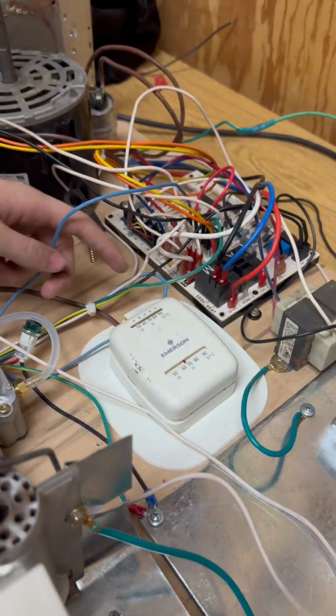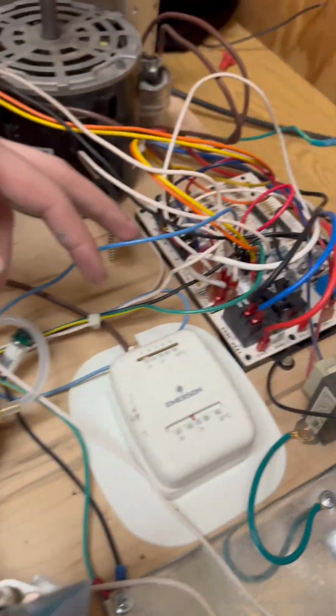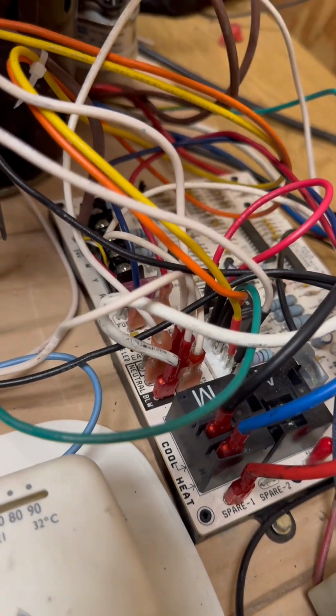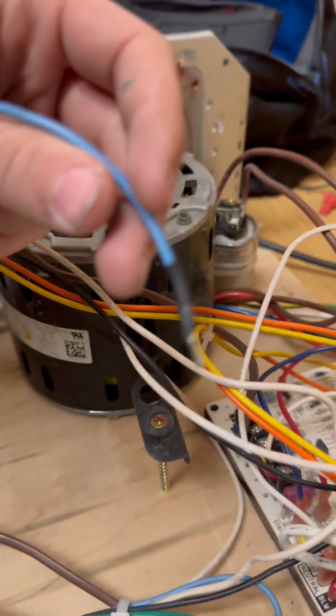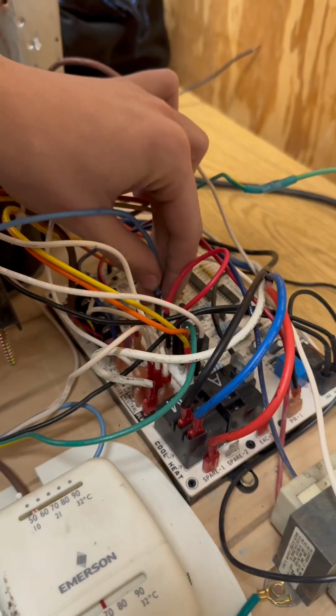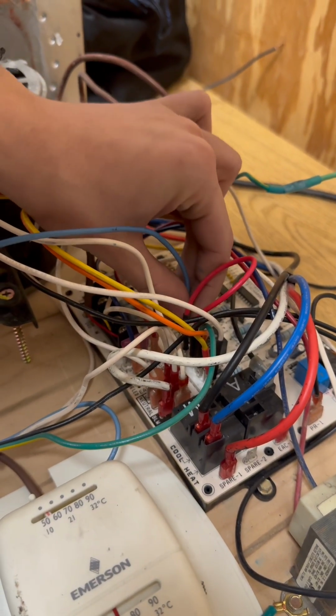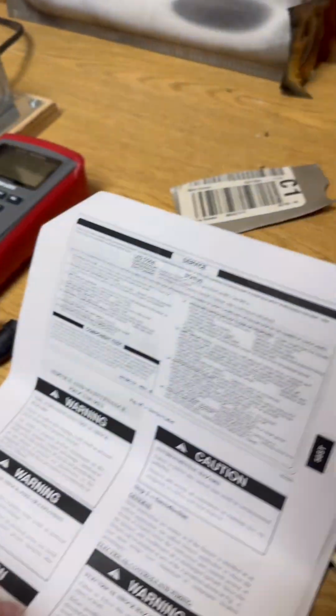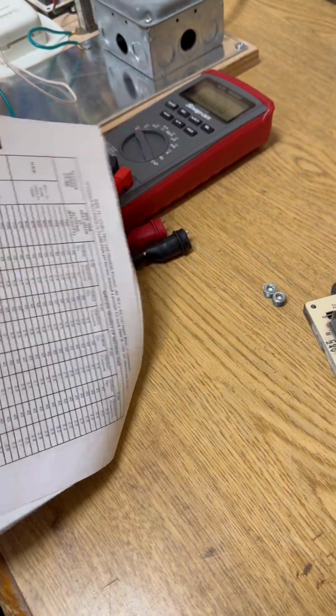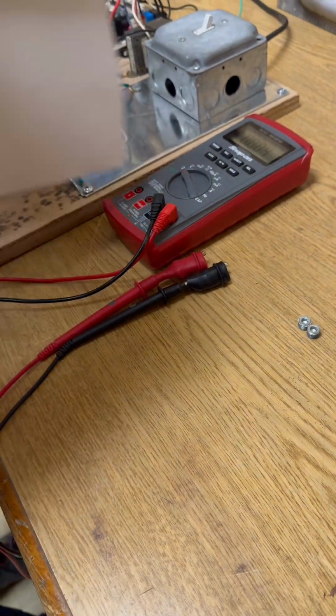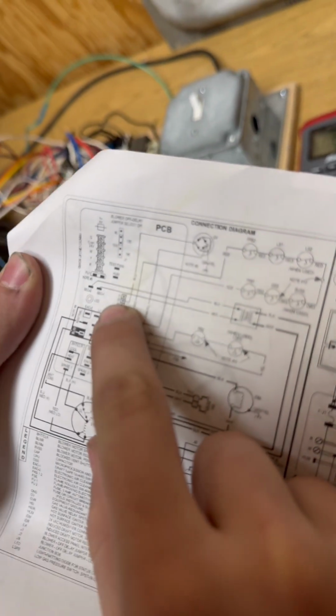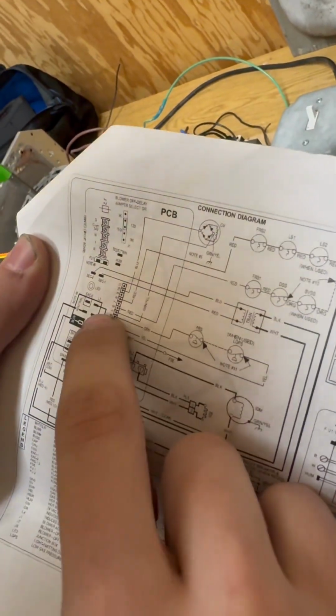So we traced our wires from our gas valve back to our board and found out that we had a bad crimp on one wire. So we have since replaced that. And now I'm going to replace that onto our board. Make sure it's on the right pin, which you can find on our schematic. So we're going to ensure that our gas valve, which is up here, is blue, is hooked up to pin 10, and green and yellow is hooked up to pin 5, which we have confirmed on our board.